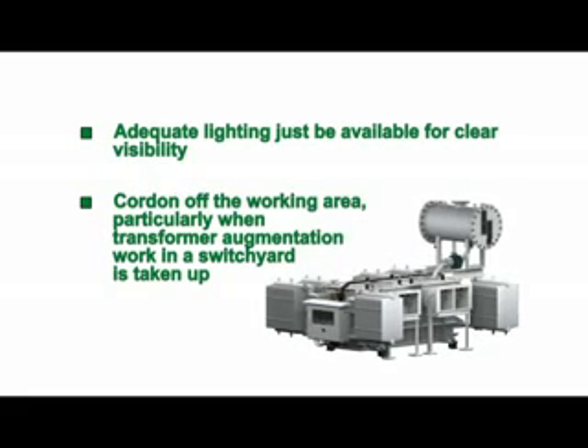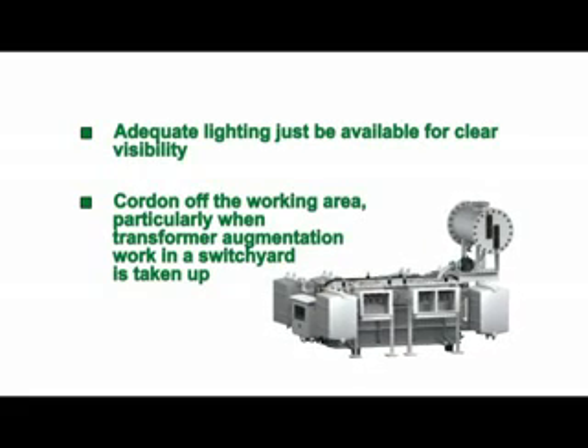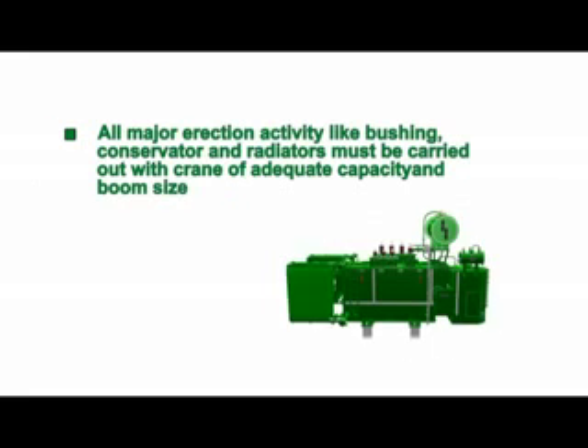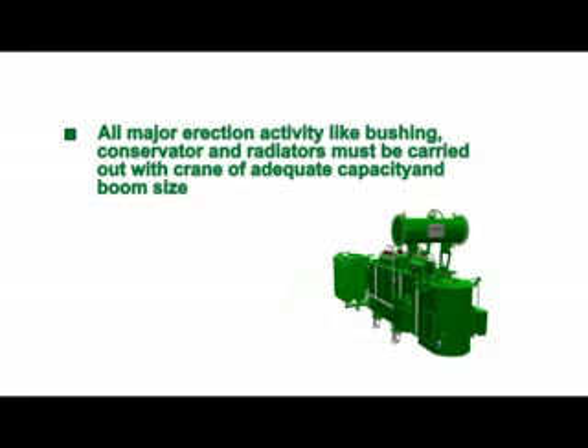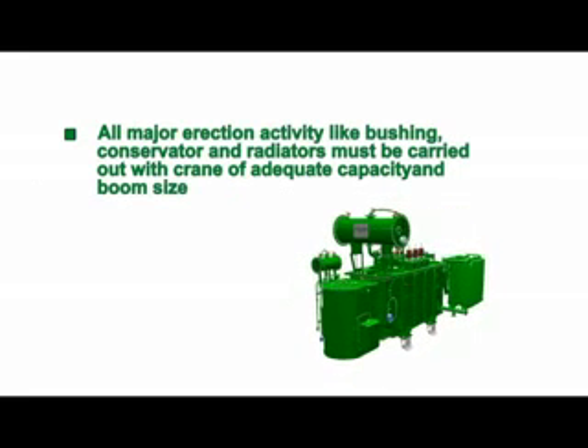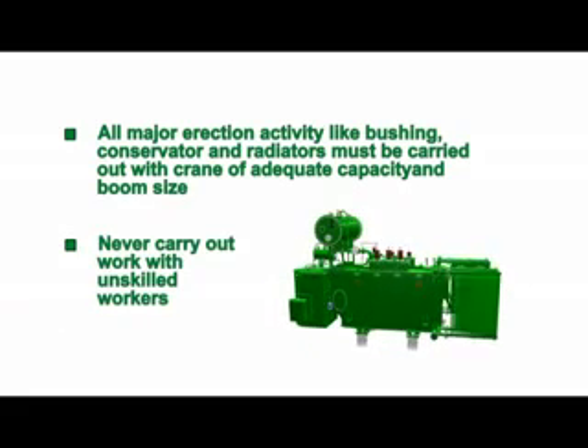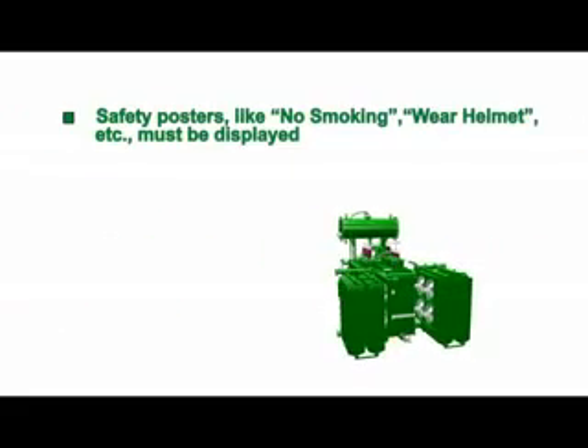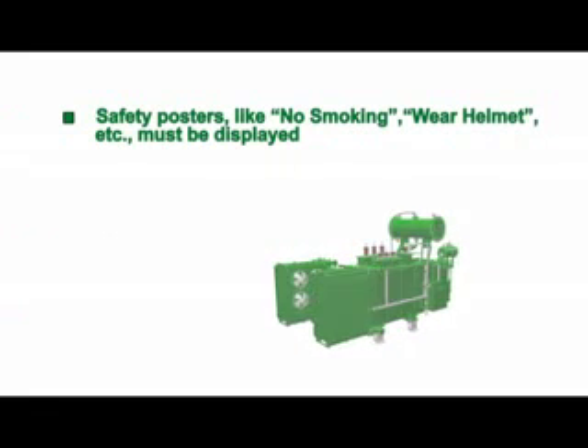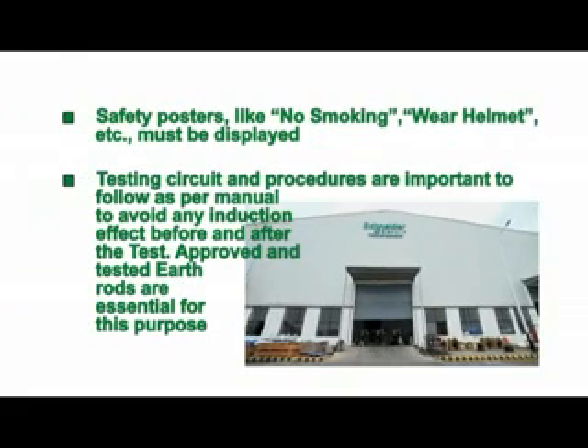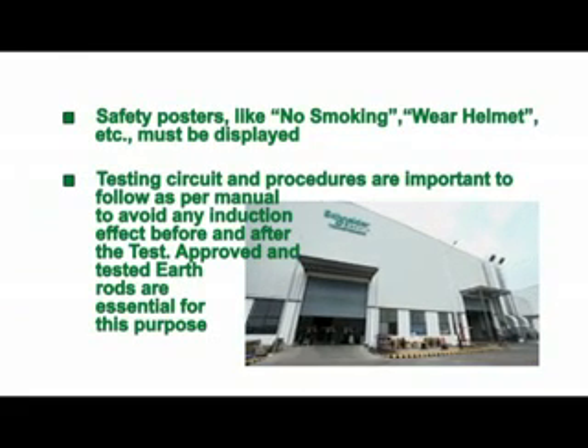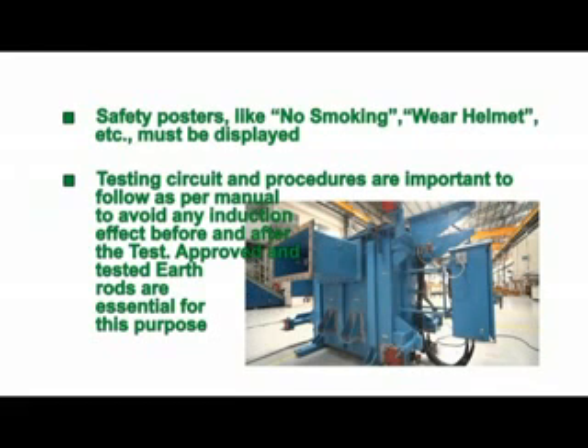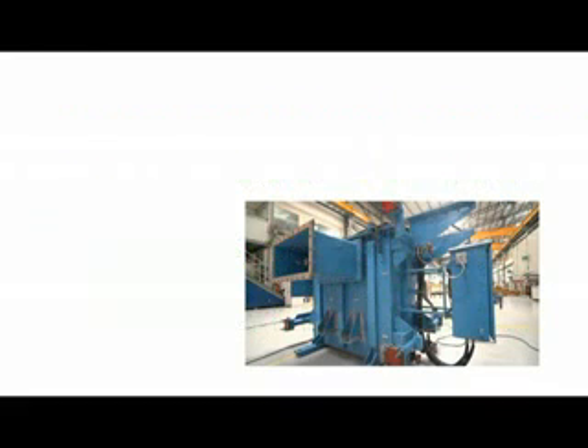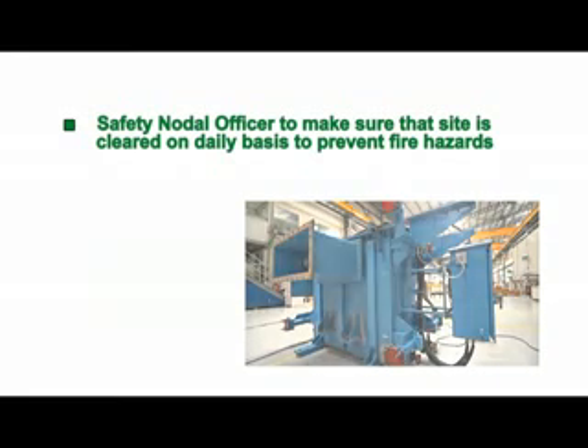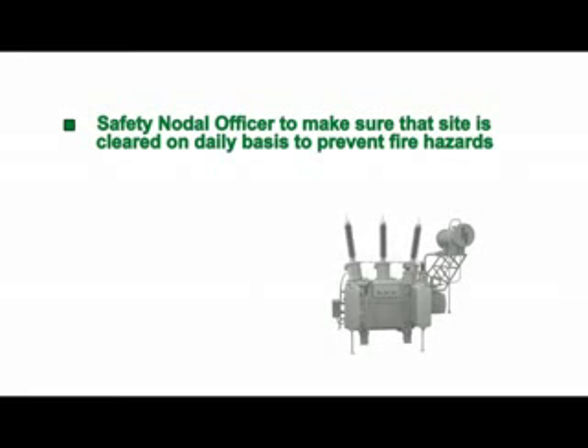Cordon off the working area, particularly when transformer augmentation work in a switchyard is taken up. All major erection activity like bushing, conservator and radiators must be carried out with a crane of adequate capacity and boom size. Never carry out work with unskilled workers. Safety posters like no smoking, wear helmet, etc. must be displayed. Testing circuit and procedures are important to follow as per manual to avoid any induction effect before and after the test. Approved and tested earth rods are essential for this purpose. The safety nodal officer is to make sure that the site is cleared on a daily basis to prevent fire hazards.